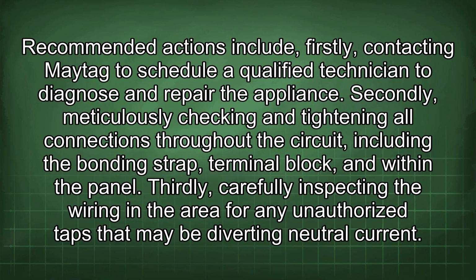Recommended actions include: firstly, contacting Maytag to schedule a qualified technician to diagnose and repair the appliance. Secondly, meticulously checking and tightening all connections throughout the circuit, including the bonding strap, terminal block, and within the panel. Thirdly, carefully inspecting the wiring in the area for any unauthorized taps that may be diverting neutral current.